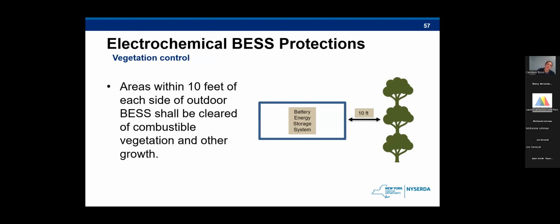So here for the vegetation control, any areas within 10 feet of an energy storage system must be clear of all vegetation except ground cover vegetation like grass. This I think is pretty obvious as well. It's required to prevent a fire spreading to different locations outside the enclosure if there is a fire outside the enclosure. But once again, you are allowed to reduce this clearance to combustible vegetation based on your large scale fire testing. So that once again would be totally up to the fire code official, but I think we're mostly seeing projects really sticking with that 10 feet.